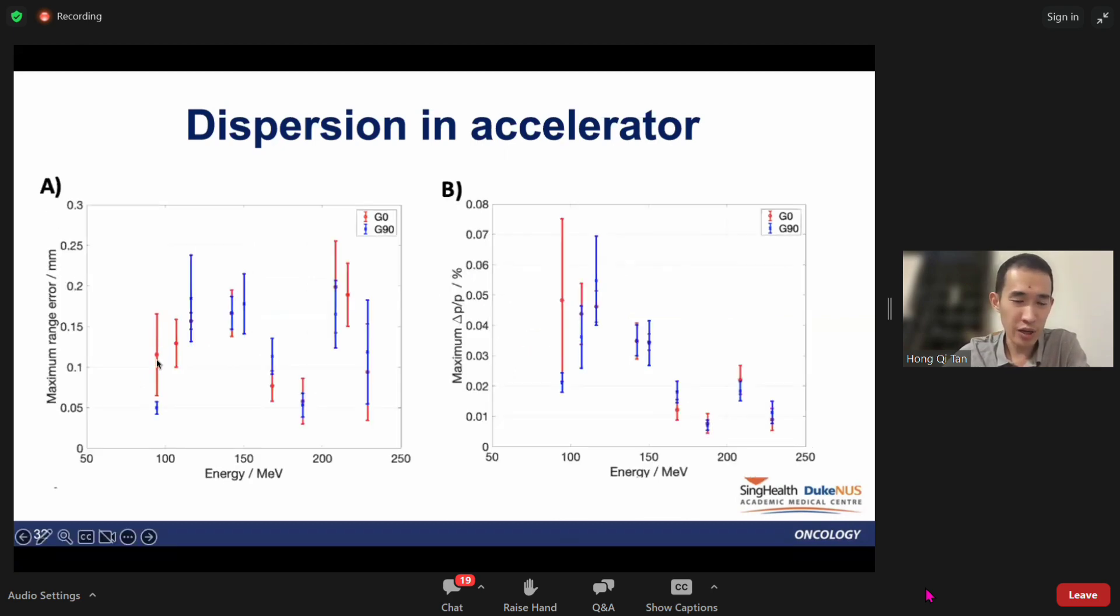If we look at the maximum range error in these measurements, most of the range errors are less than 0.3 mm. From TG-224, which is the QA report for proton therapy, the tolerance limit for range errors is 1 mm in daily and monthly QA, so we are well within this tolerance limit. The maximum delta P over P that we registered is less than 0.08%, and Hitachi promised us less than 0.2%, so we're well within the Hitachi limit as well.